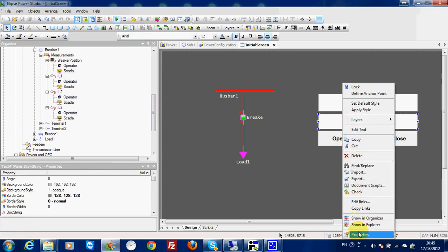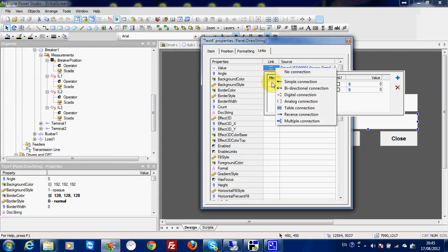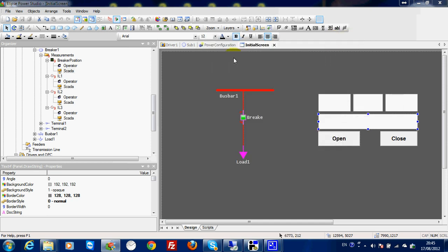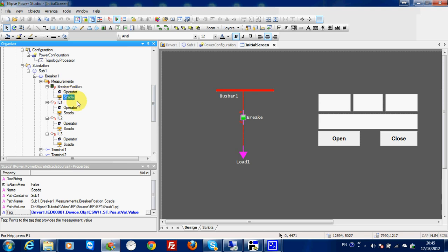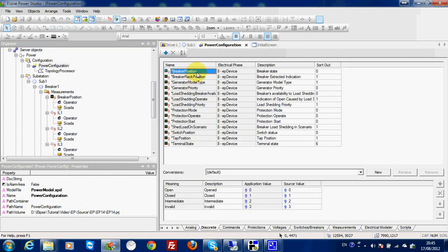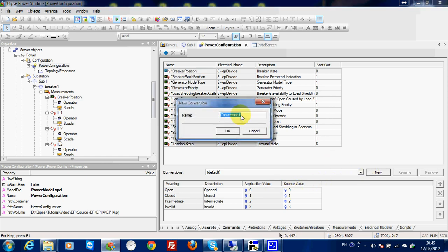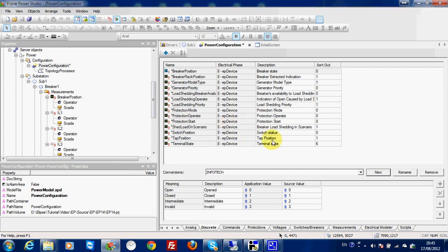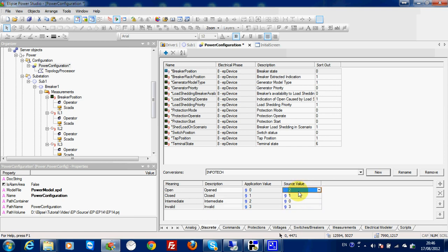From my previous video, I made a link which tells me that closed is 1 and open is 2. So in my breaker position SCADA, I have the value, but I need to keep in mind that open is 2. In my configuration I need to go to discrete breaker position and apply a conversion. Open is 2, but by default open is 0. So I can make a new conversion and call it 'infotech', which is the name of my relay. Here I can apply: 2 for open, 1 for closed, 0 for intermediate, 3 for invalid. So I have the correct conversion for my relay.